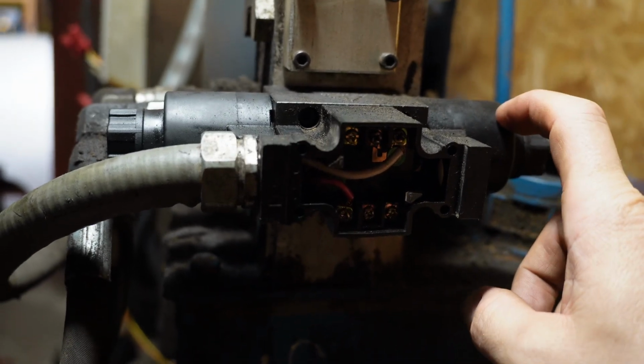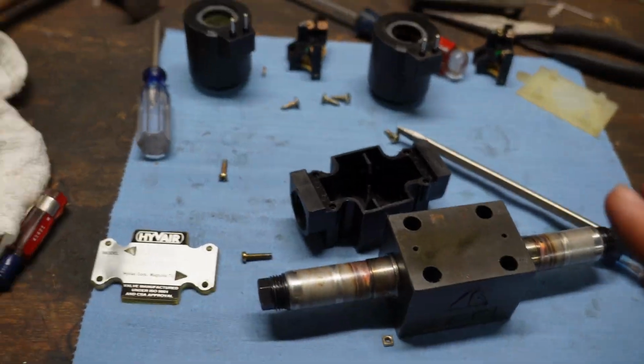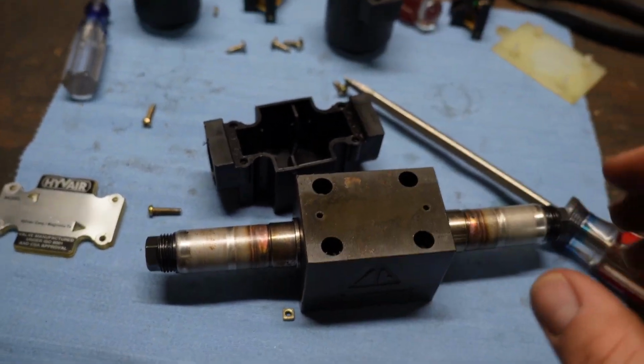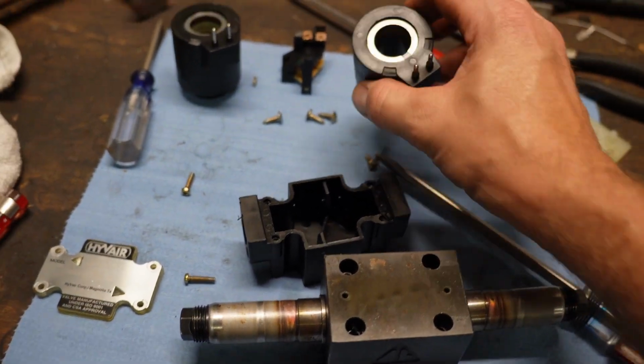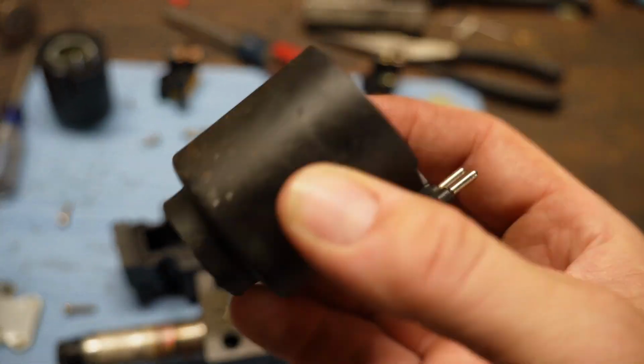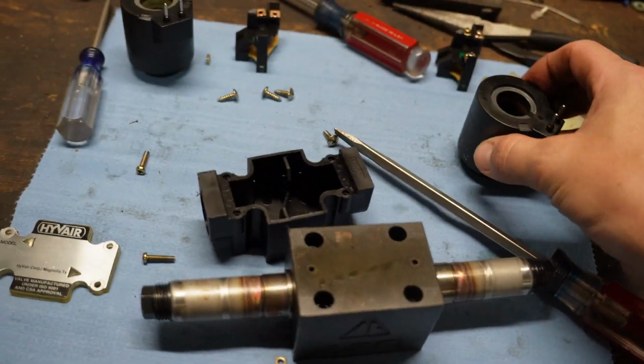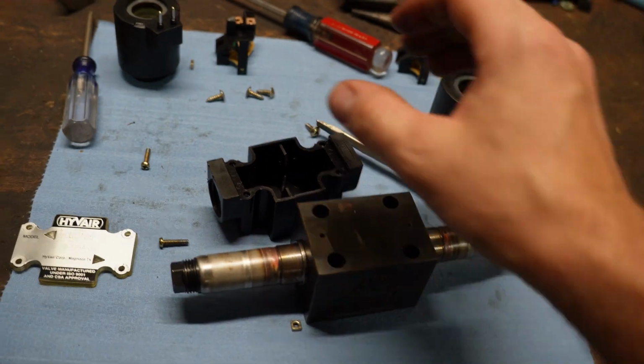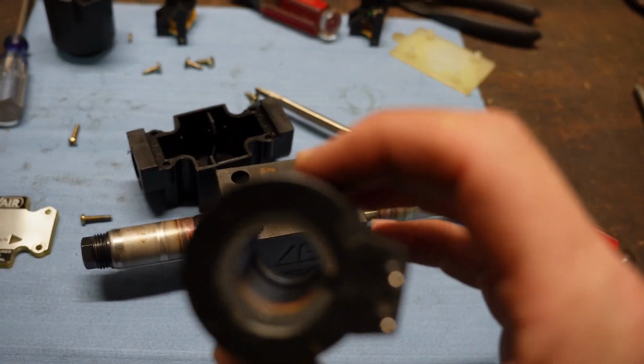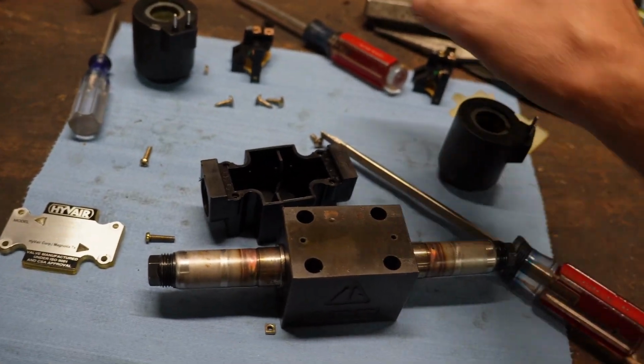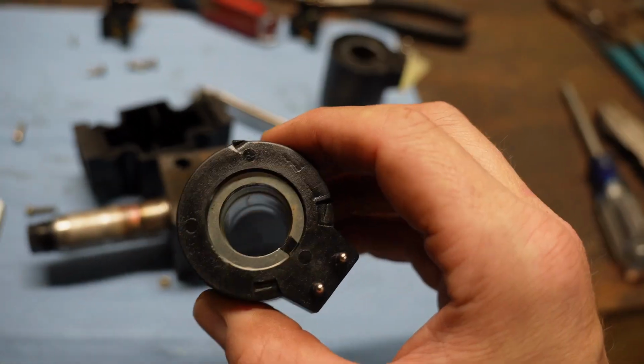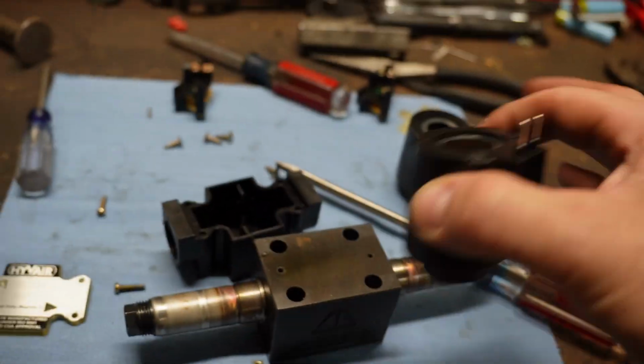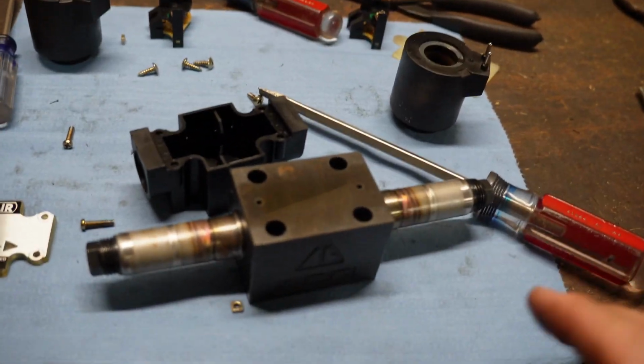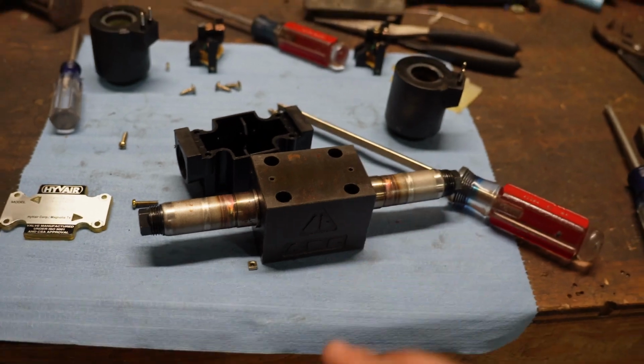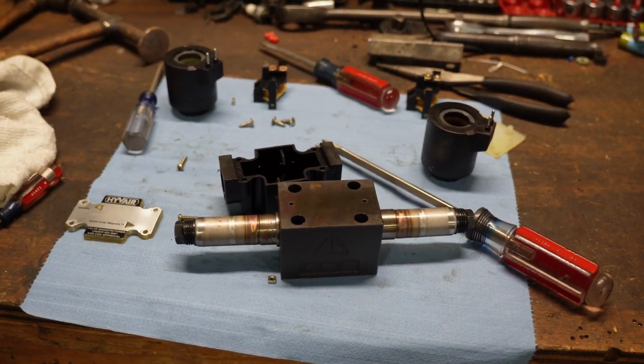So I took this whole thing off, threw it on the bench. And on the bench here, now this is a separate one. Fortunately, I had a second one, but I found out that one of the coils on the other one was bad, and that was this one here. See how brown that is in there? So this one had one good coil on it, and then this coil, which was bad. So out of the two valves together, I was able to make one good valve.